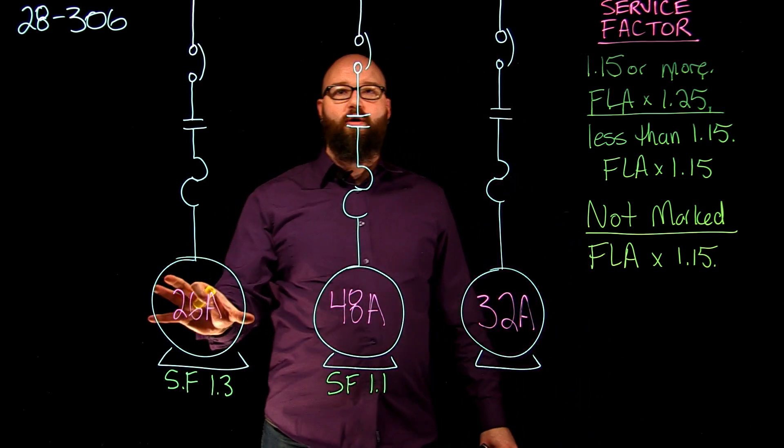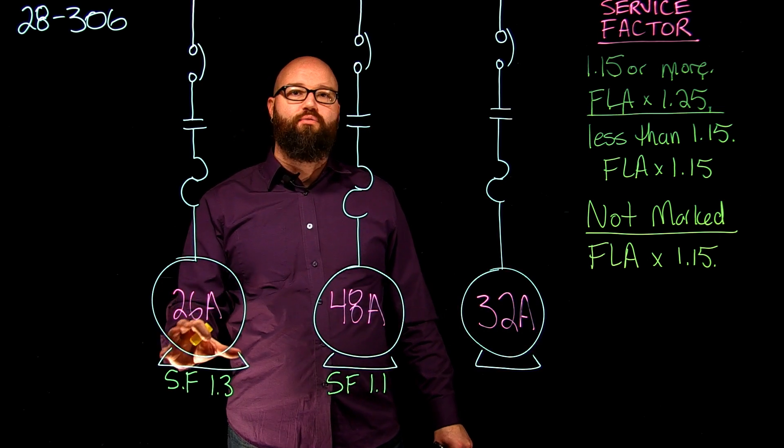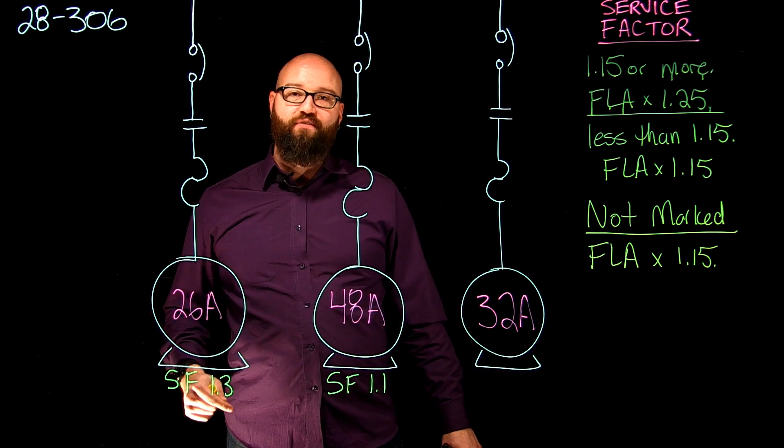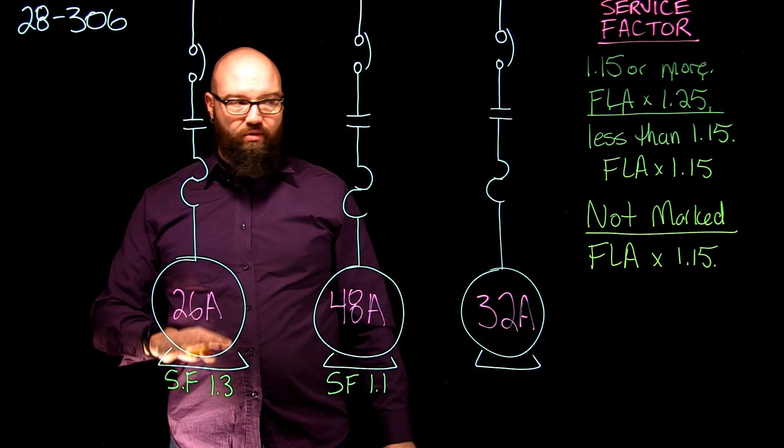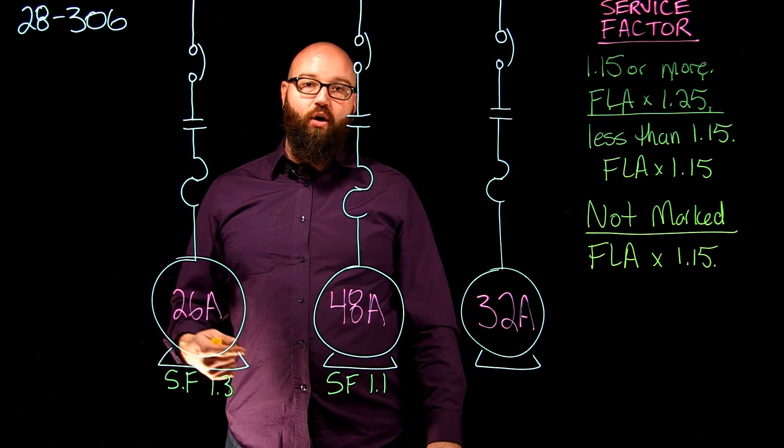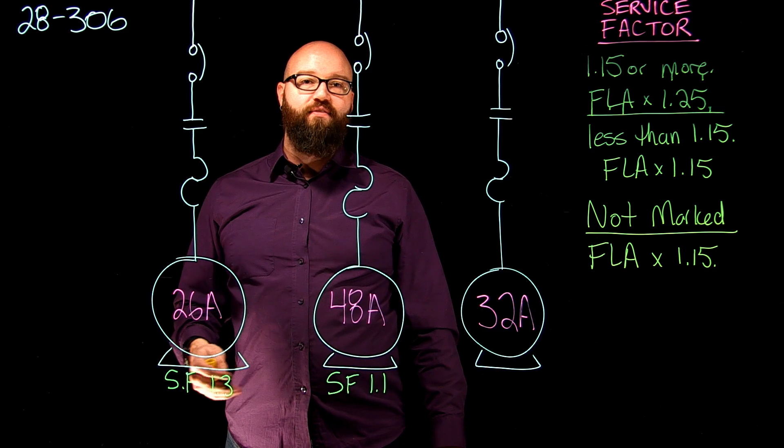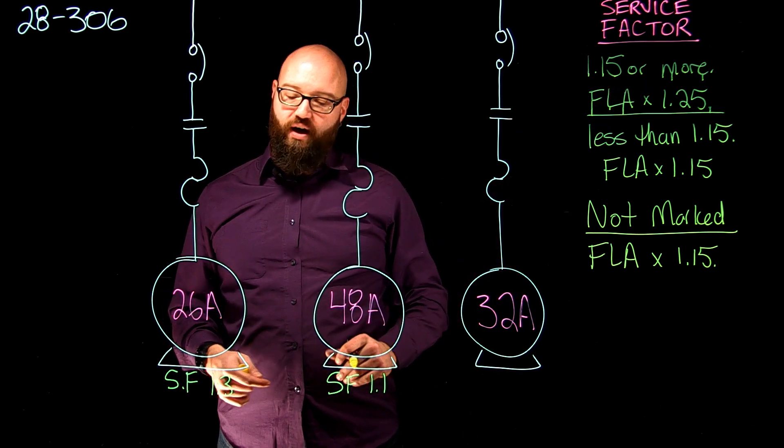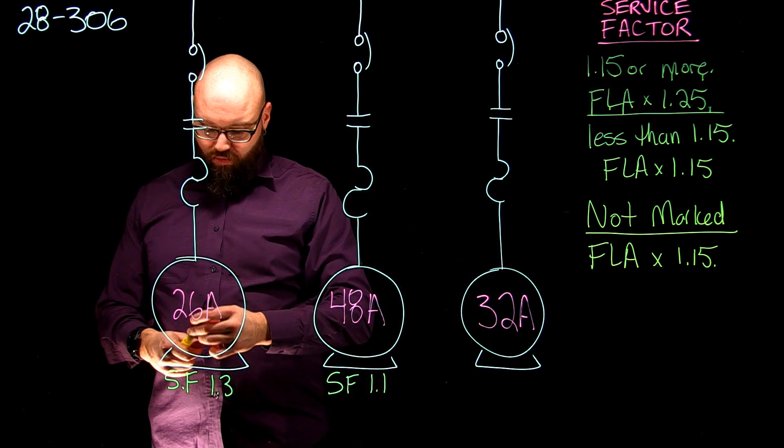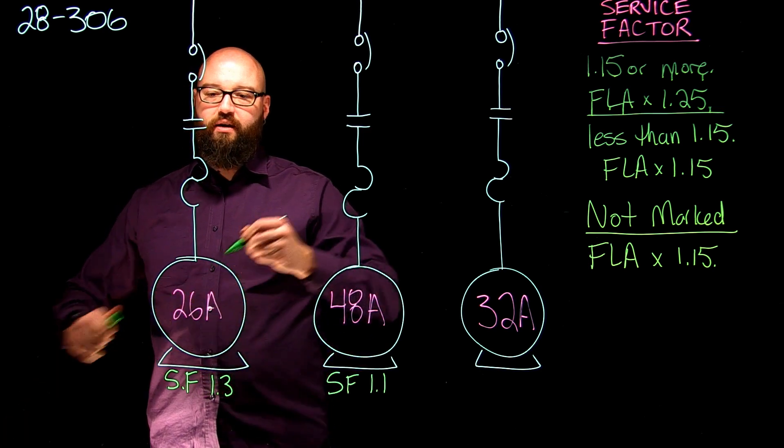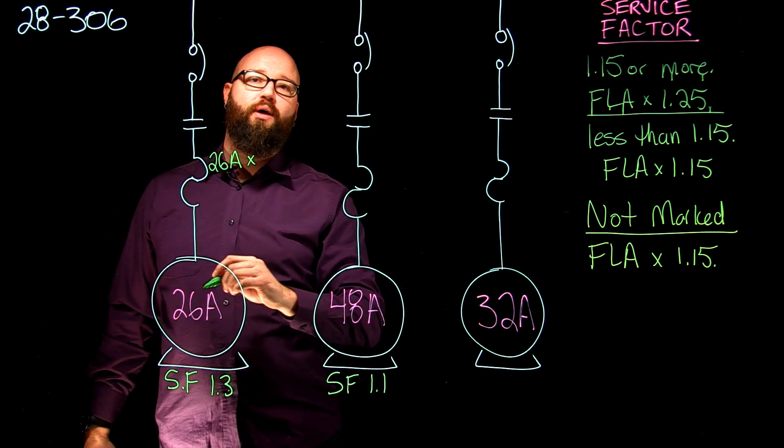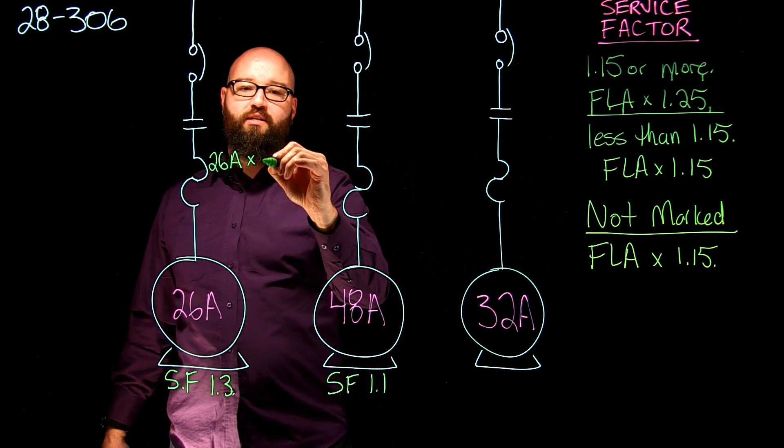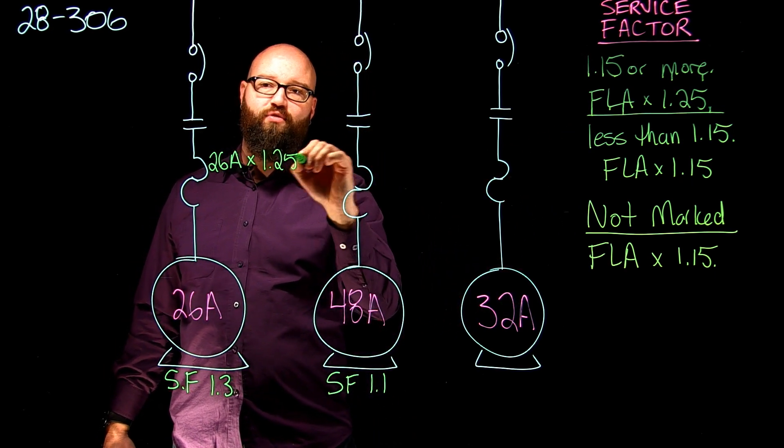The first one we have, we have a marked service factor of 1.3 and an FLA of 26 amps. According to what we just talked about, that service factor is larger than 1.15, inclusive of 1.15. So we're going to take that number, that 26 amps, and we're going to multiply it by 125%, so times 1.25.